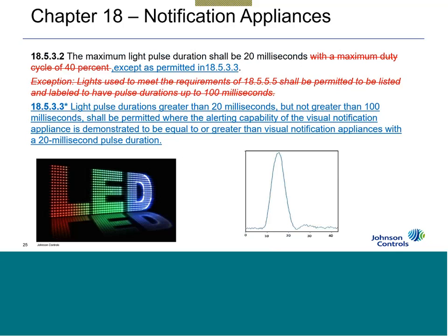So let's change to strobes for a minute. When LEDs came on scene, there have been issues where not all LEDs are created equal. Some LEDs are more intense than others. Some ramp up, hit their peak intensity, and ramp down rather quickly. Others take a little bit longer. What was being found through research at NFPA was some LEDs were taking a relatively long time, 100 milliseconds, to ramp up and ramp down, and weren't hitting their peak intensity quick enough to alert you.